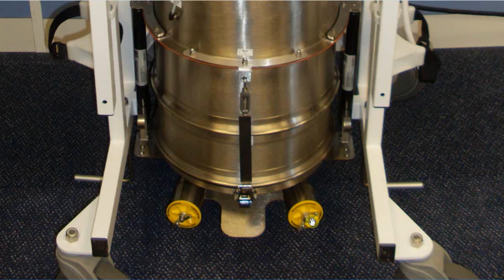And as mentioned briefly just now, if the machine has a problem or the batteries are flat and you wish to ventilate, then the manual breathing tube will fit snugly over this connector here on either side once the bungs have been removed, and in that way the manual breathing circuit can be used to ventilate a patient like a standard rebreathing circle system for any horse.